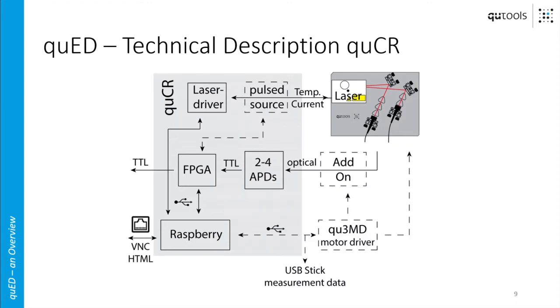An interesting feature is that you have a network connection at the back, so you can communicate with the Raspberry computer via the VNC protocol and copy the display for presentation purposes — for example if you want the quCR screen on the projector. You also have a very small HTTP protocol accessible via network with which you could program your own applications. Of course you can also connect a USB stick to collect measurement data and analyze it further on a computer.